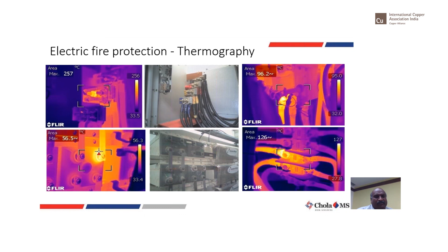Do proper preventive maintenance, thermal imaging, and all of that. And don't always think, okay, we have asked the guys to do it, because they find ways and means of getting things done. If you see on the left-hand side, you asked him to terminate it. He knows how to terminate. At the end of the day, the supply is there. Yes, he's going to put a test lamp or a plug and check whether supply is available. But see the quality of the termination that he has done.